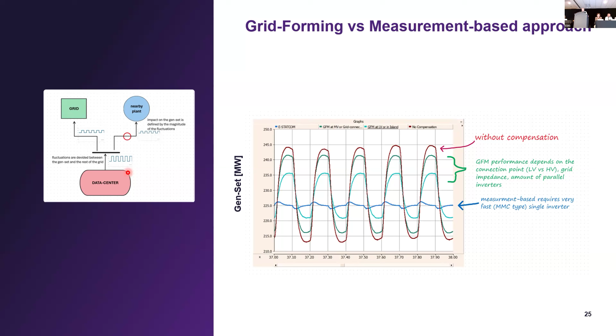The control philosophy that we utilize here is actually the same one we've been using for the last 20 years for arc furnace compensation, because arc furnaces have a very similar problem, and it's a very straightforward approach. Basically, you measure the load and you react to these measurements. So if the load jumps 100 megawatts, you compensate all 100 megawatts exactly. But for this, you require a very quick response time.